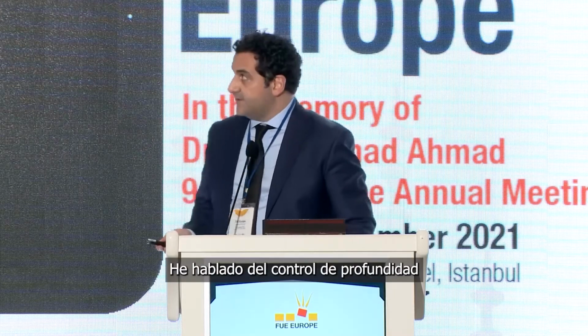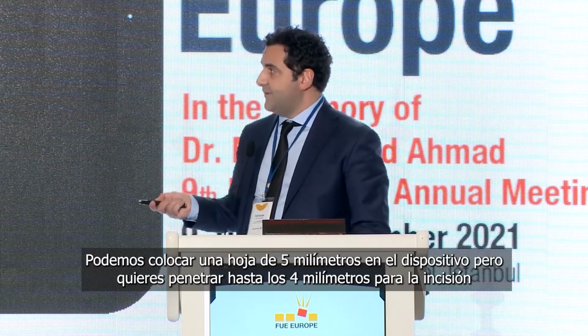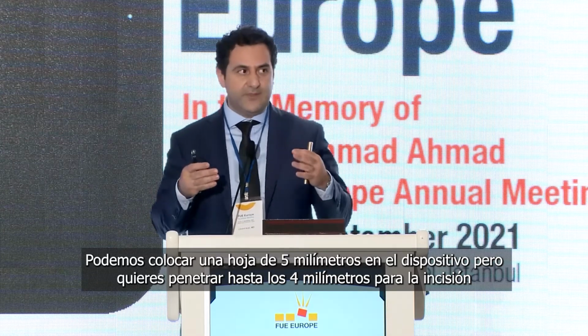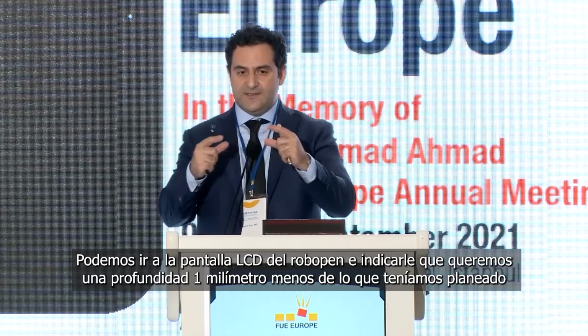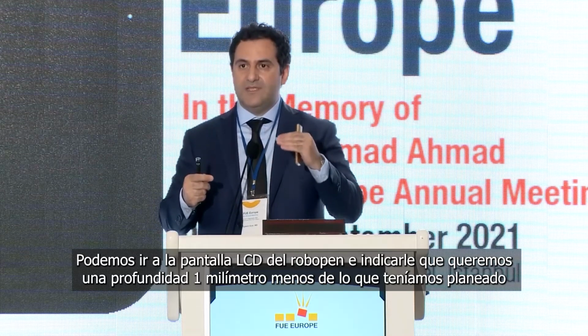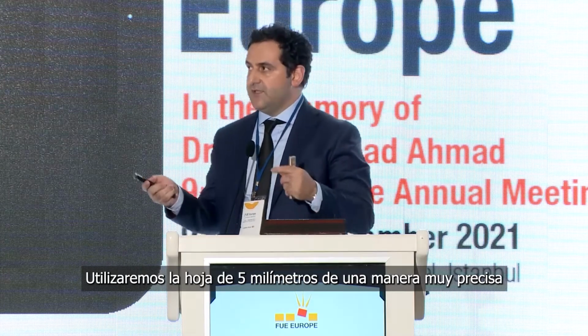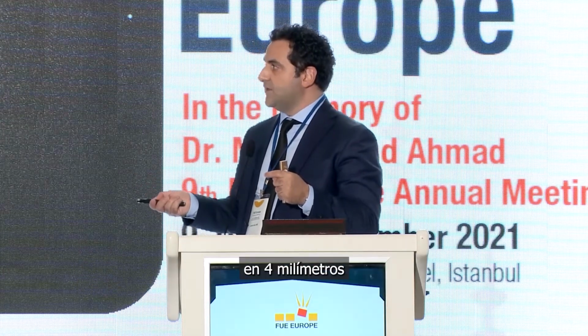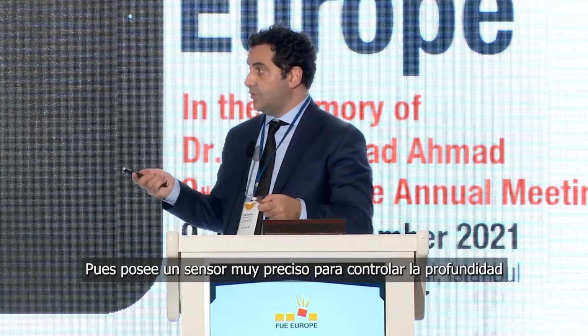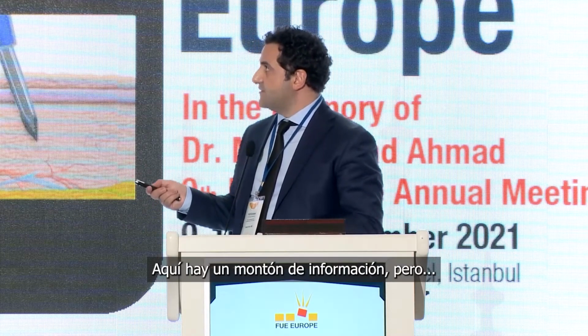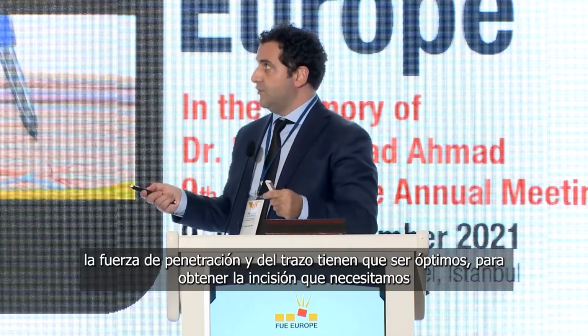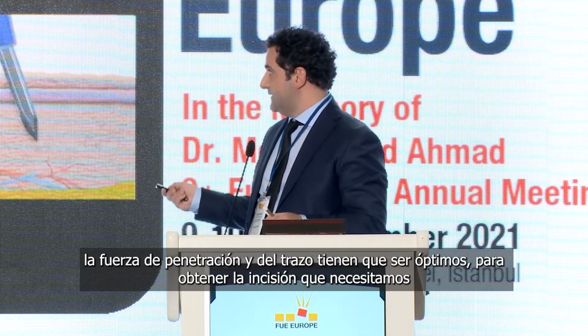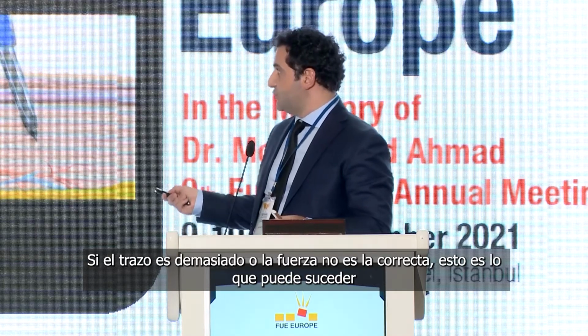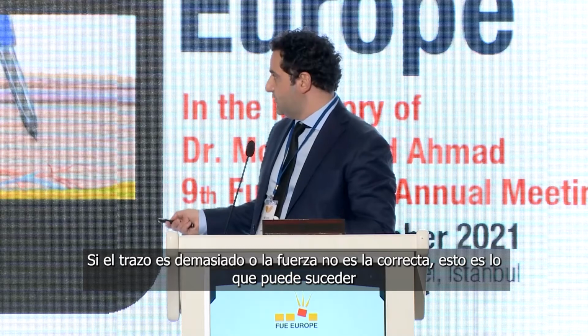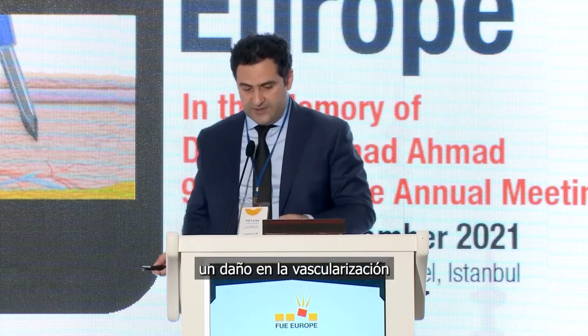Here I will speak about depth control. For example, you can put a 5 millimeter blade on the device, but you want to go just 4 millimeter for the incision. You can come to the LCD screen and give the order to go 1 millimeter less deep than what I planned. You can go with the 5 millimeter blade very precisely, only 4 millimeter. So it has a very precise sensor to control the depth. And here this is a long piece of information, but this is about the force we are using and the stroke. The force and stroke must be optimal to get the incision we need. If the stroke is too much or if the power is too much, then this can happen: blood circulation damage.